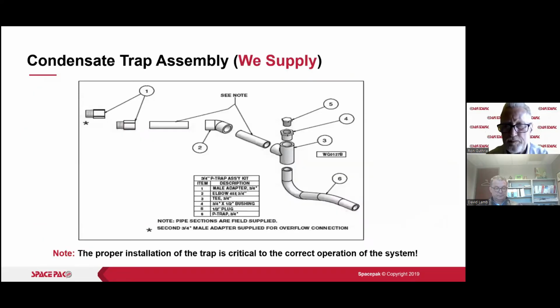Okay. All right, so this is usable for both heat pump and cooling. Again, we give you a trap. Use that trap. It's deep enough to compensate for being on the negative side of the fan. So just keep that in mind. We need a deep trap, and if we don't have that, what the unit will want to do is pull air up through that trap and not allow proper drainage.